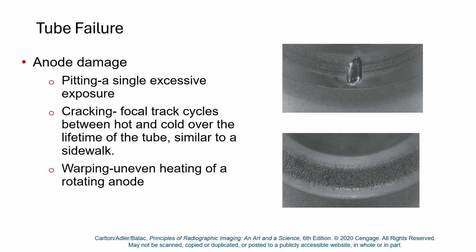Okay, so the software has basically fixed our ability to create pits in our x-ray tube. Now cracks, that's basically what happens to a sidewalk over time. Every night it gets colder, and then when the sun comes out during the day, it warms up. And then you repeat the process day and night, and eventually your sidewalk has gone through hundreds of thousands of iterations of heating up and expanding, and then shrinking back down at night and contracting. And that over time produces physical stress in the concrete, and cracks develop.